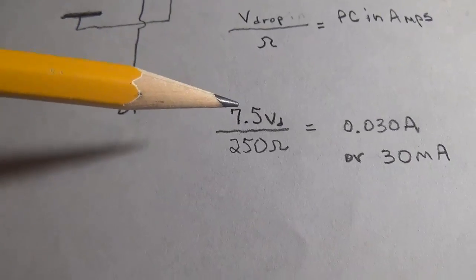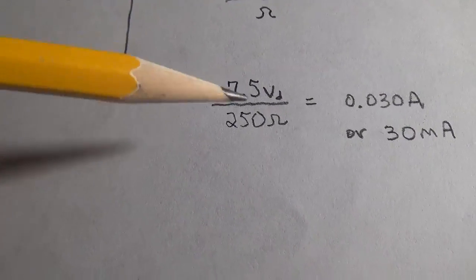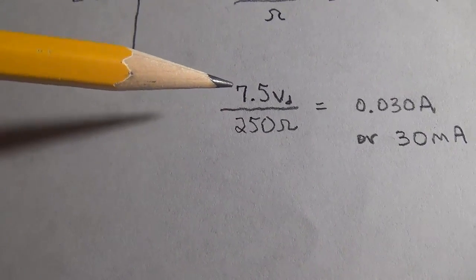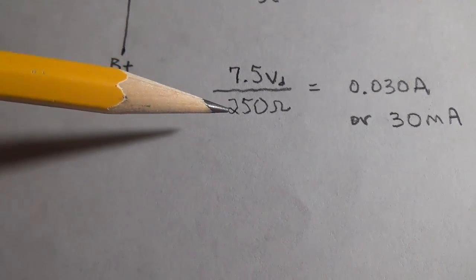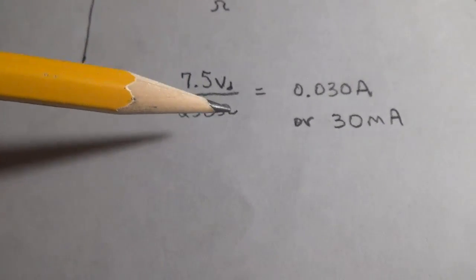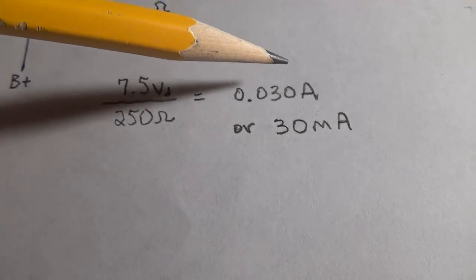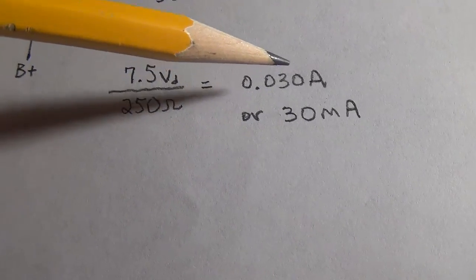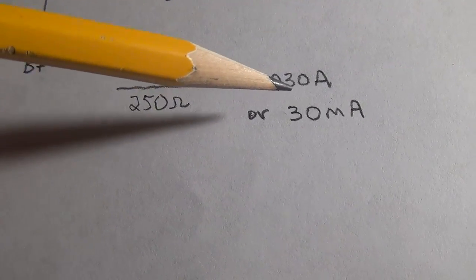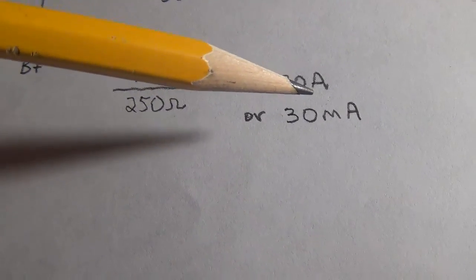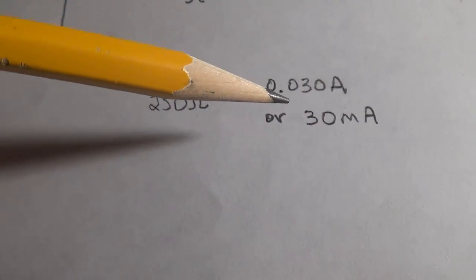Then we look at our measurement and put it into this formula, where it is the voltage drop divided by the resistance of the half winding, and we get that answer in amps - it's 0.030 amps. Or you can move the decimal 3 points to the right and change it to milli, meaning 1,000th of an amp. Go 3 to the right and we have 30 milliamps.